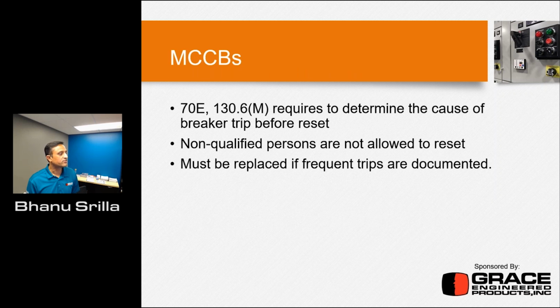Okay, so MCCBs. One point I came across is 130.6, which requires you to determine the cause of a breaker trip. This is something most of us do even with residential breakers: the first tendency, if something trips, is to go and reset it without knowing why it tripped in the first place. 70E specifically requires, in Article 130.6, that you determine the cause of the breaker trip before you reset it. There could be a fault on the other side, and that's why the breaker tripped. You need to make sure you're not going to close on the fault.